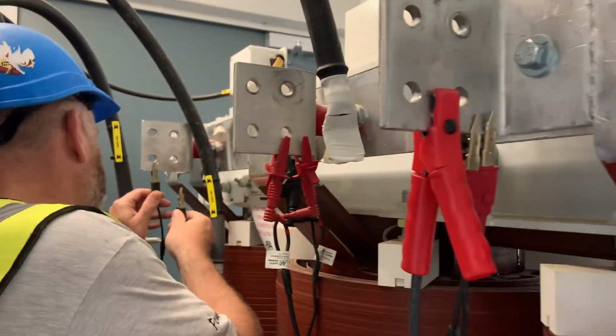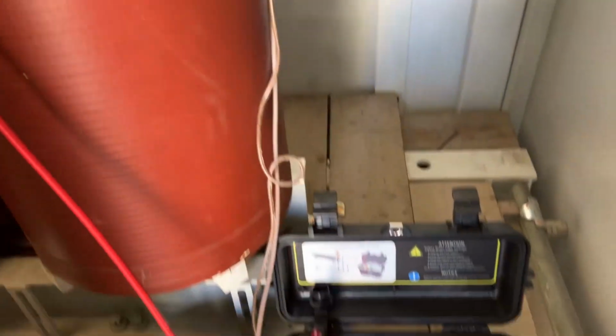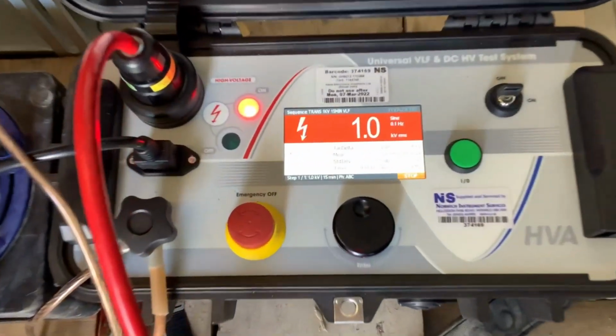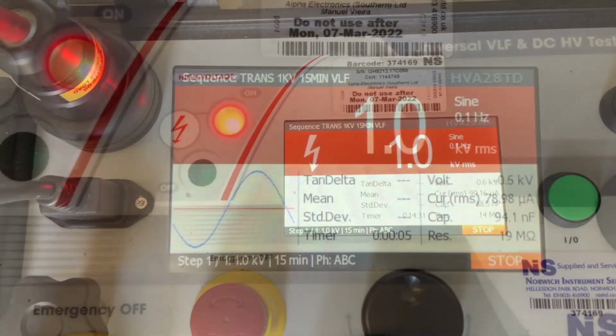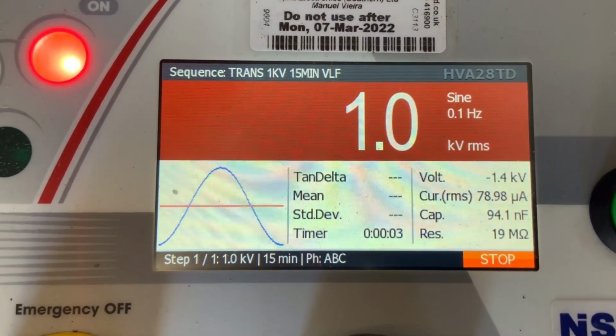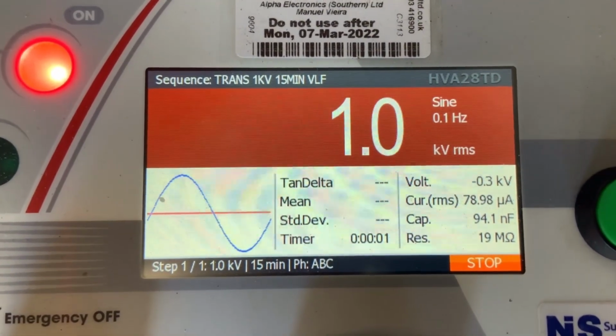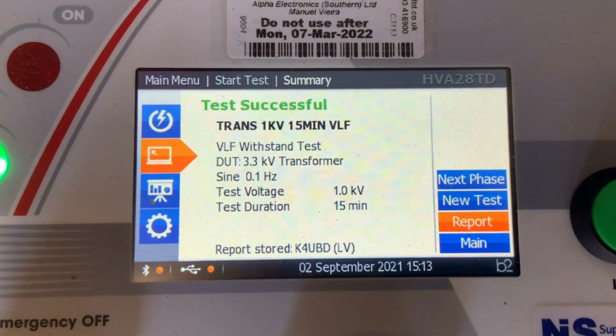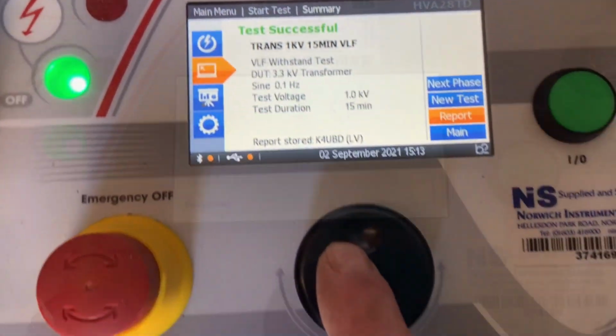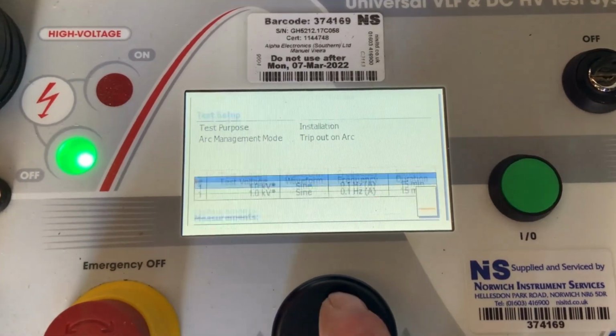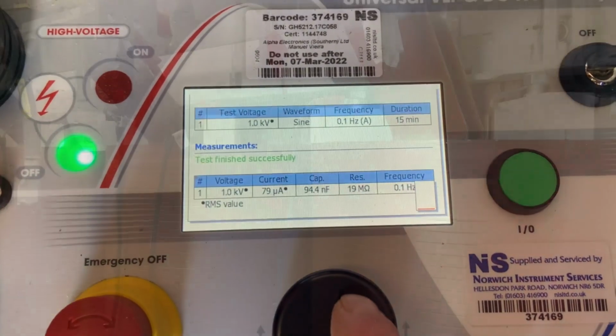The second test we want to do is basically a repeat of the HV test. We want to short the LV windings together and apply this time 1 kV RMS VLF to the windings and check the resistance of the windings down to earth. Okay, we can generate the report from that now.